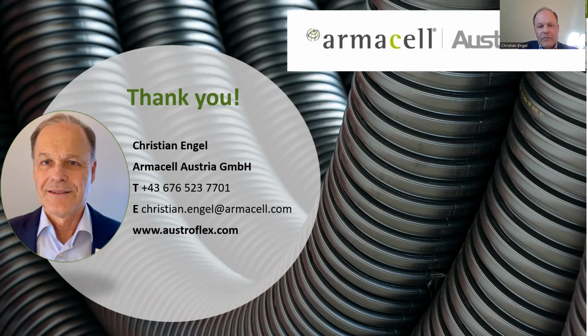From my experience, more on the plastic side than the steel side, how you operate the network is extremely important, apart from the installation side, how you control the temperature levels. We have seen from our cooperation partners, from the very beginning in the 1980s, that they have networks in operation without problems when they constantly control the flow temperatures and keep them below 80 degrees.